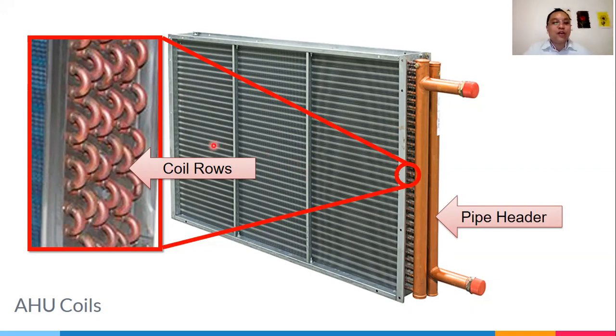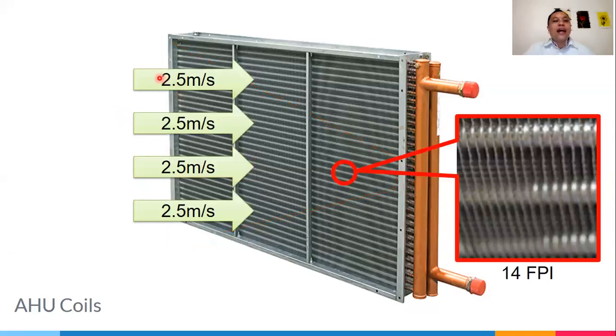If you really don't bother much on how much the pressure drop, then how deep your coil is doesn't really matter. But if you are worried about your fan pressure drop, the fewer the coils, the lesser the pressure drop. Usually, the manufacturer will always size your coil at this inlet velocity. To have efficient heat transfer from your air to the coil, it is recommended to have a velocity near 2.5 meters per second. So if you would see your coil manufacturer's calculation, no, they would always have this 2.5 meters per second velocity through the coil.